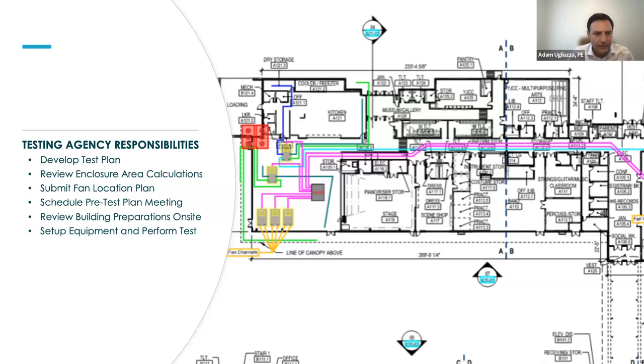Schedule that pre-test meeting. So at that point, you've got the plan, you've got the location plan. You can go through that with everybody that's important to the test. Everybody should walk away from that meeting having a really good understanding of what's going to happen. Reviewing the building preparation part. That's typically something that the general contractor is going to perform. Mechanical equipment, shutting them down, sealing them up, opening up interior doors, removing ceiling tiles as required. On bigger buildings, it's a lot of work. So it really needs to be planned out ahead.